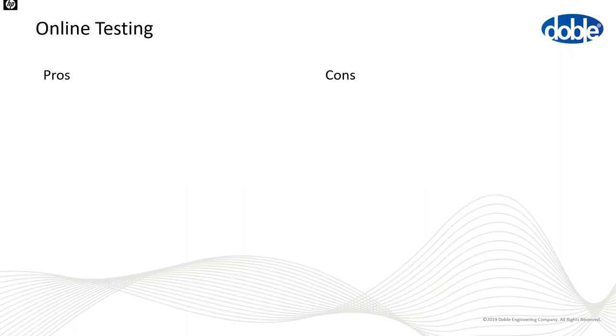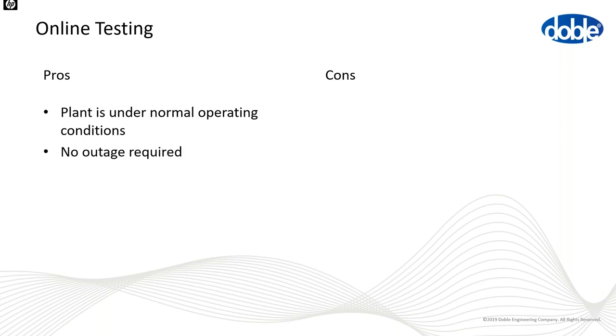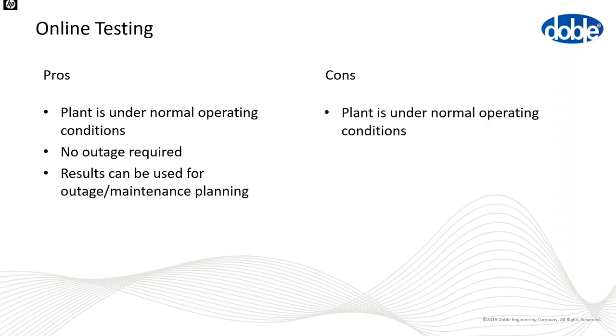Online testing has pros and cons. A key pro is that the plant is tested under normal operating conditions, so we see it as it is most of the time — no outages required, and results inform outage and maintenance planning. The cons: the plant is under normal operating conditions, meaning all external noise that could interfere with measurements is present. There is also a limited set of measurements we can actually perform online.